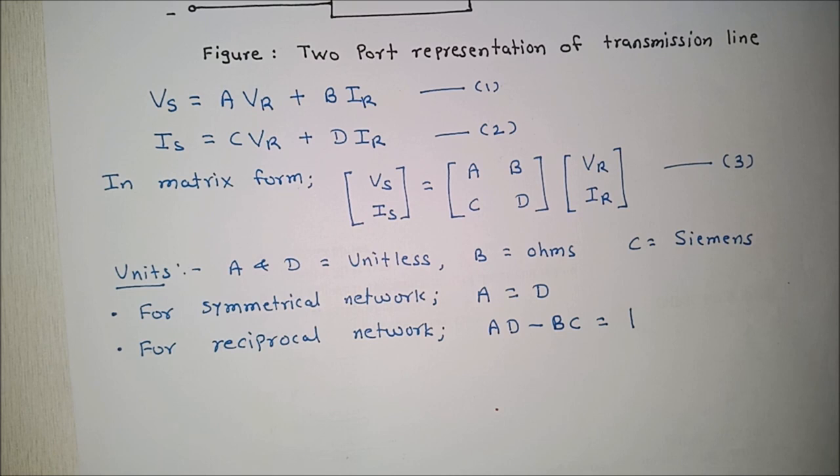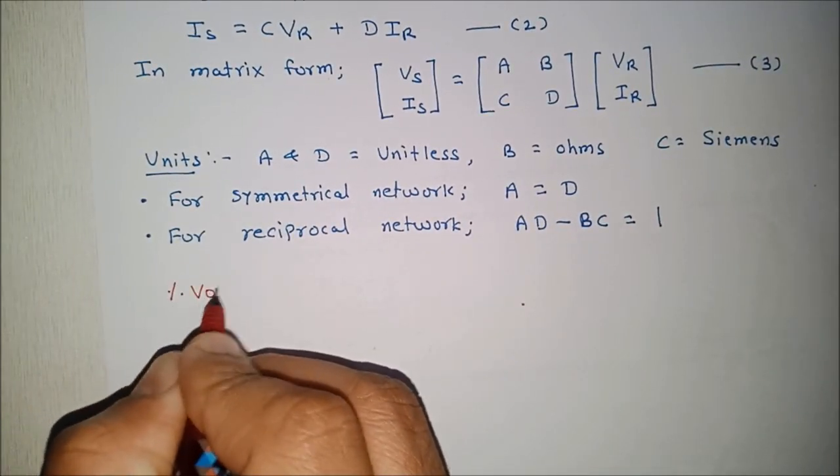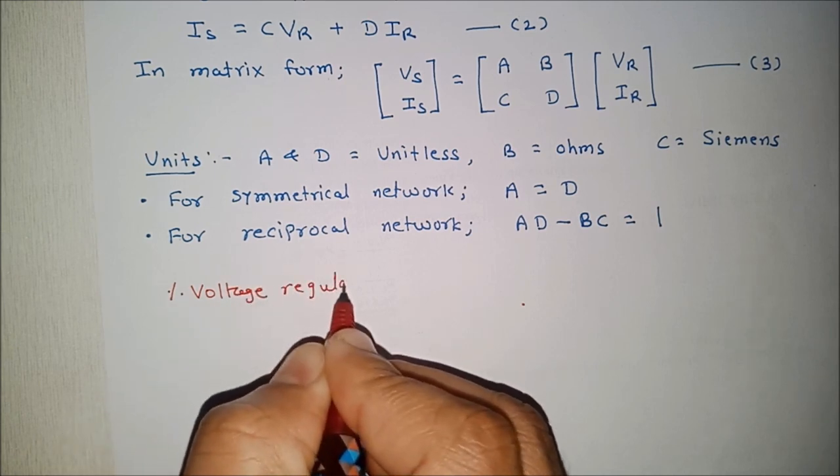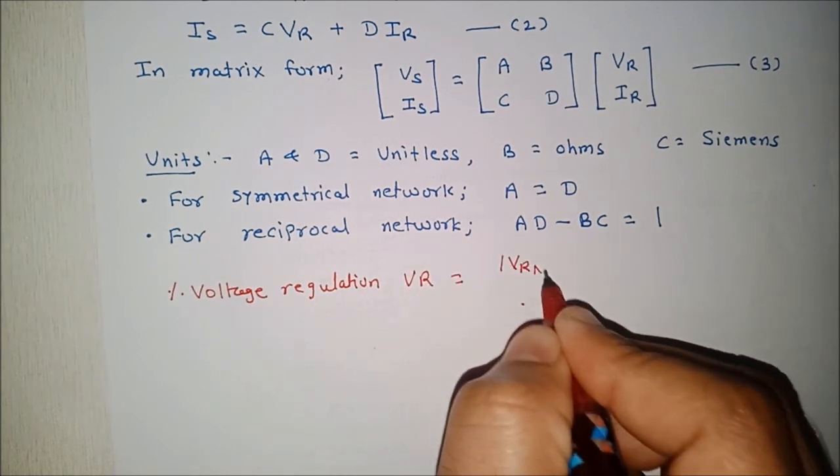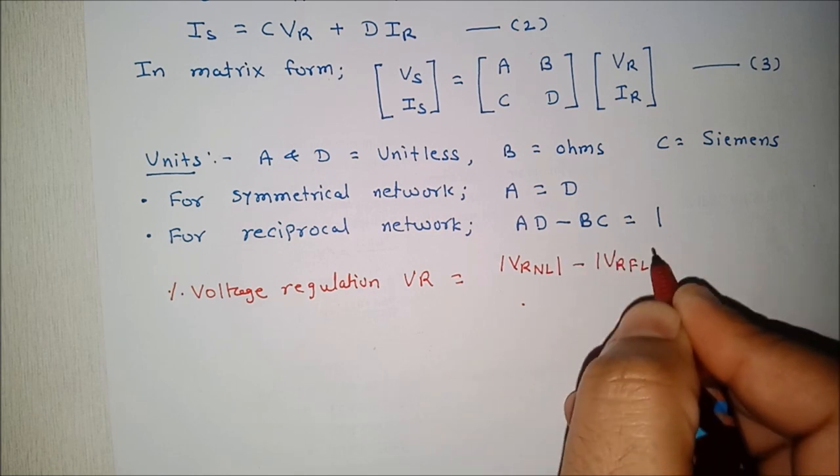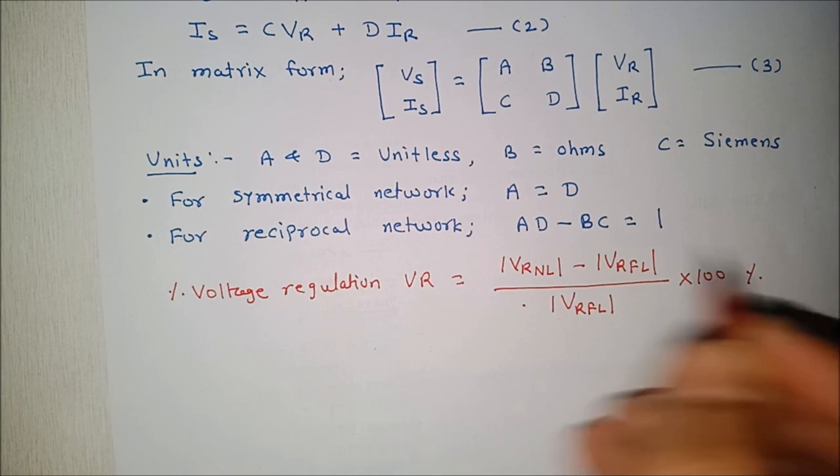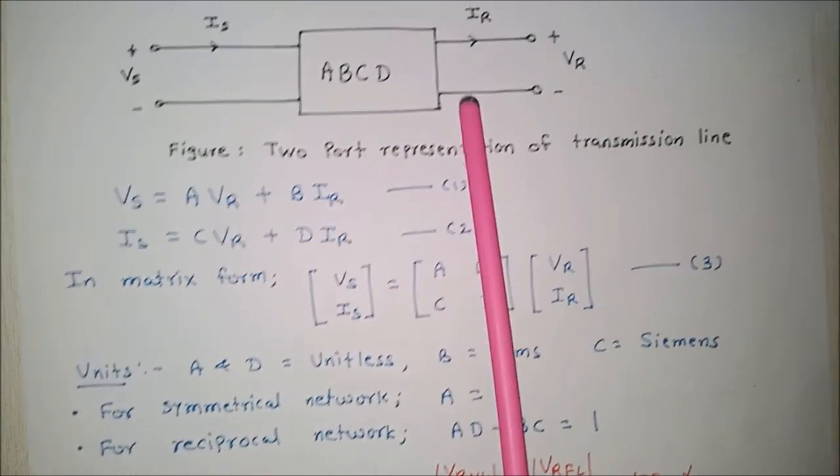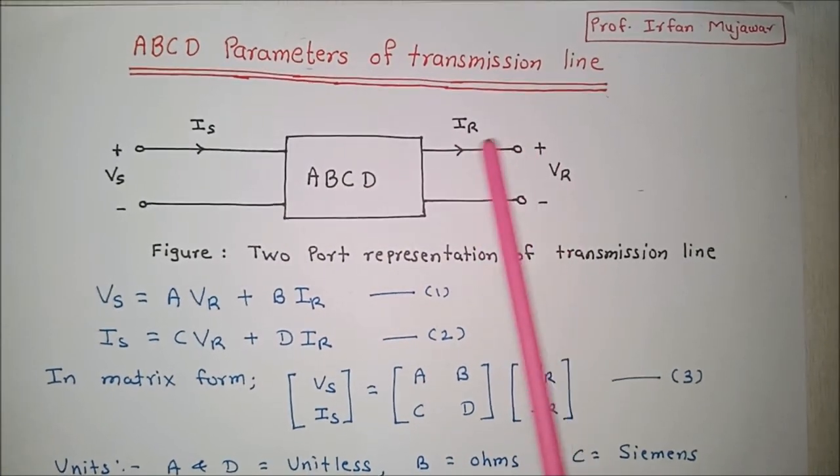Now how to determine the voltage regulation? Now we know that voltage regulation of transmission line, so percentage voltage regulation of line Vr, it is given by Vr no load minus Vr full load divided by Vr full load into 100 percentage. Now how to obtain Vr no load? Now see the equation number 1, when we say there is a no load condition, what it means is that no current will flow through the load. So, Ir will be 0.